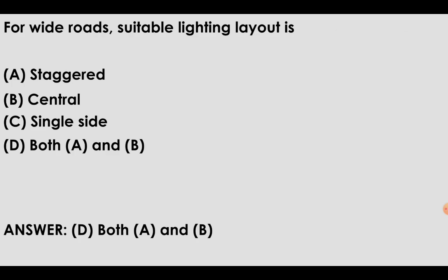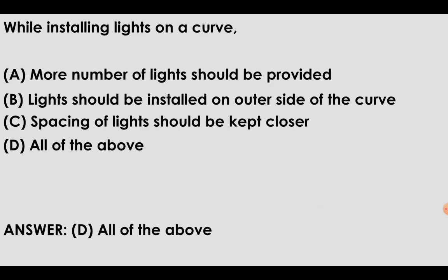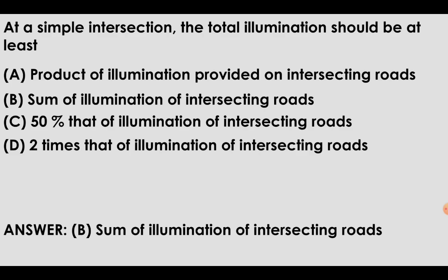For a wide road, a suitable lighting layout is staggered as well as central. While installing lights on a curve, more lights should be provided. The lights should be installed on the outer side of the curve and the spacing should be kept closer. At a simple intersection, the total illumination should be at least the sum of the illumination of the intersecting roads.